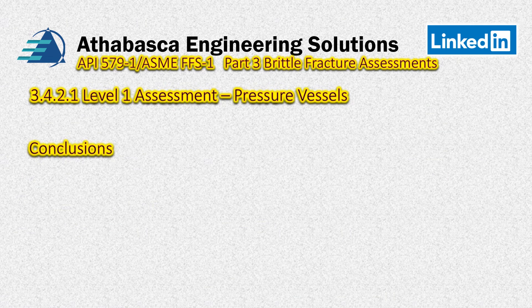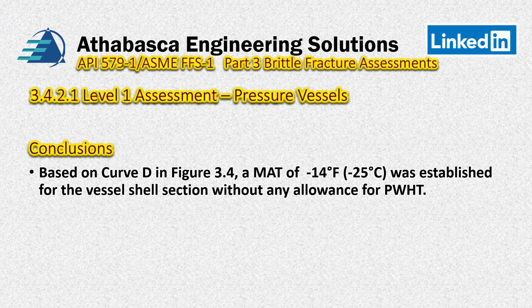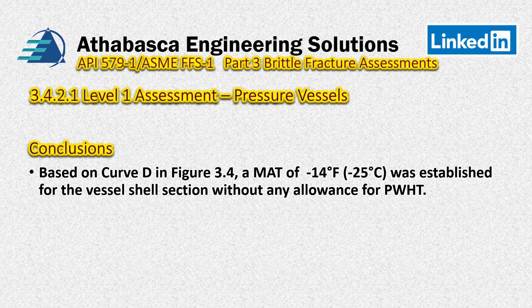On this assessment, you can tell that level one is just meant to be like a 15-minute type of analysis at a high level. Inspectors can do this, and it can be part of the report — it's just an initial check to see roughly where we are. What can we conclude? We have Curve D, and we used that in figure 3.4 to determine the MAT was minus 14 degrees. This was established for a vessel section without any allowance for post-weld heat treatment. We could have, if we had post-weld heat treating, taken more advantage and dropped that temperature more. But in this case, we stop at minus 14. If we want to sharpen our pencil, we can continue down with a level two assessment.